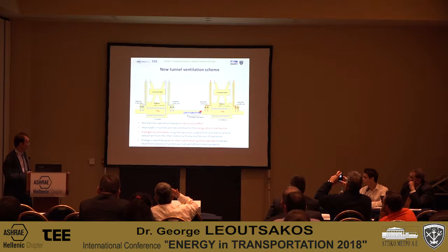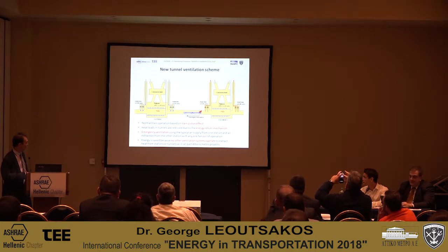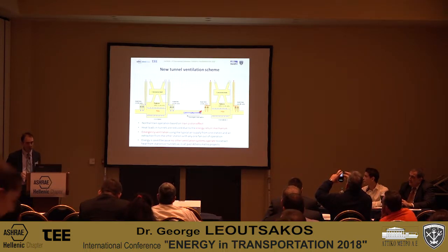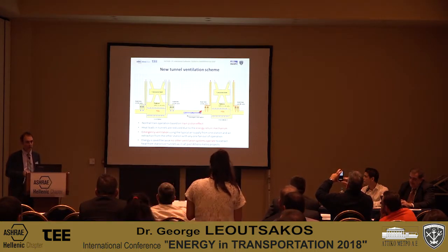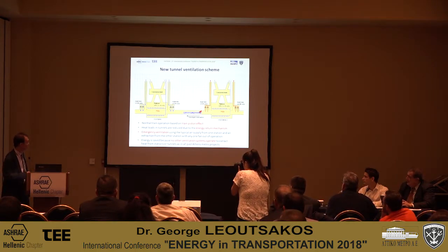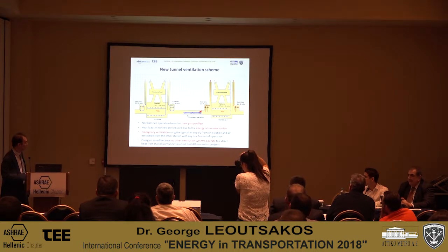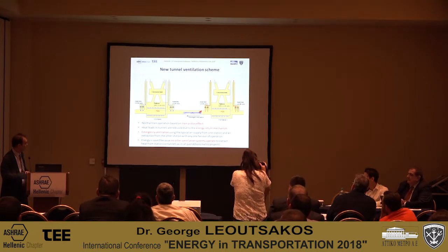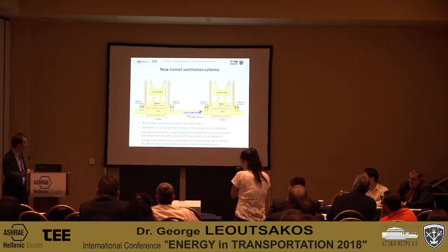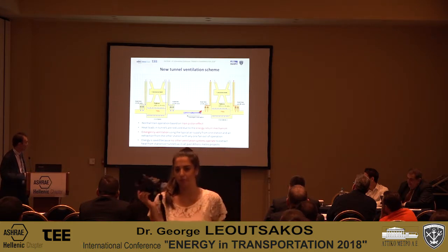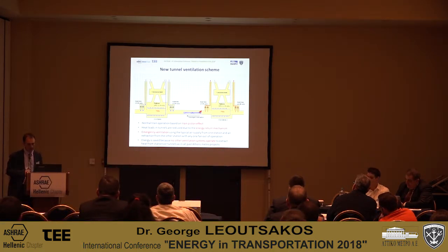So there's an additional saving of energy in this case. This is a typical layout of one station and another connected by a tunnel. At the ends of every station there are ventilation shafts, each with 2 big fans, 2 times 80 cubic meters per second. They usually will not operate during normal conditions because there will not be a lot of heat in the tunnels. If there is some heat, one of the shafts will turn on one fan at, let's say, half speed. The other shaft will be left open, creating movement of air from the open shaft to the exhaust shaft, clearing out the heat left over by the trains. So this is another way of saving energy through a more efficient tunnel ventilation scheme.